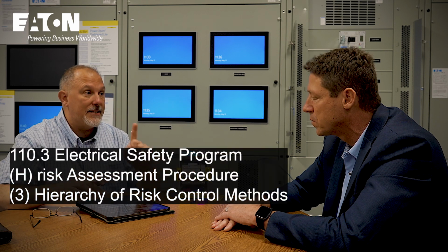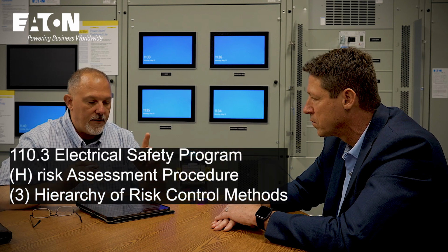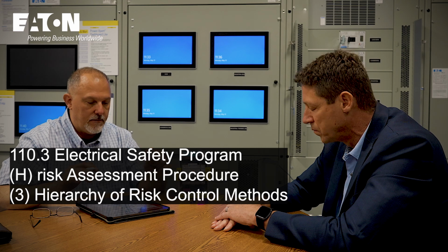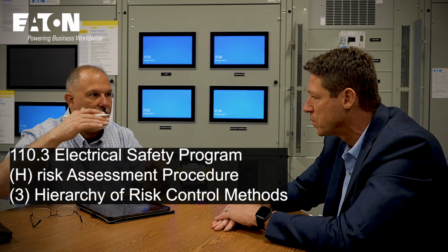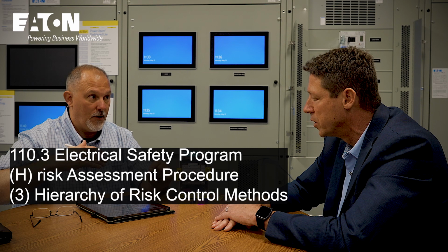110.3 in 70E is the risk assessment, and we talk about the hierarchy of risk controls. What chapter 1 of NFPA 70E is trying to drive you to is establishing an electrically safe work condition. But in thermography, can you achieve the goals of thermography while in an electrically safe work condition?